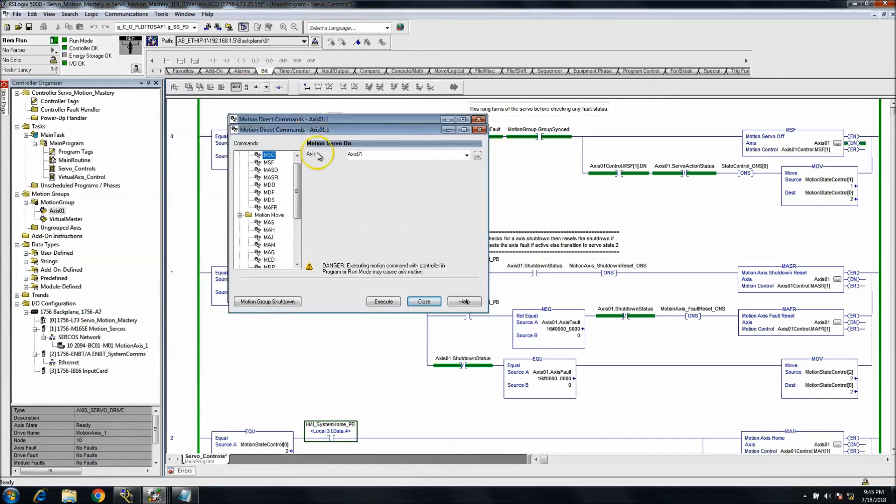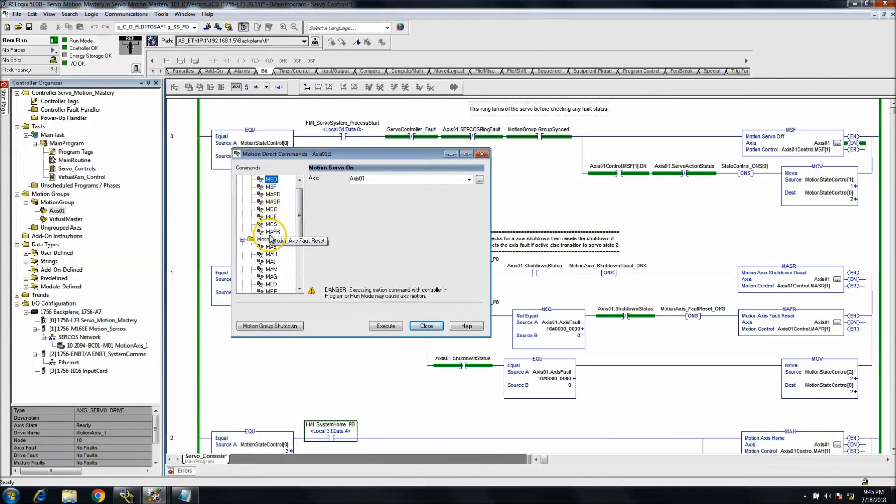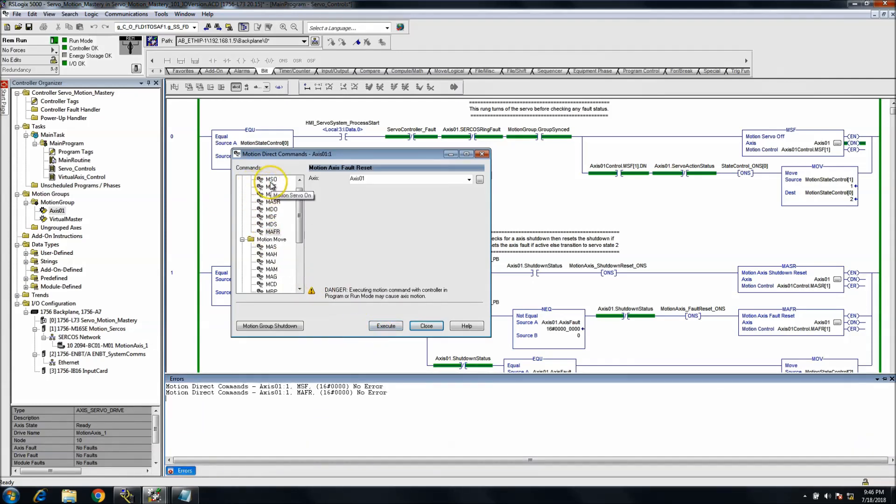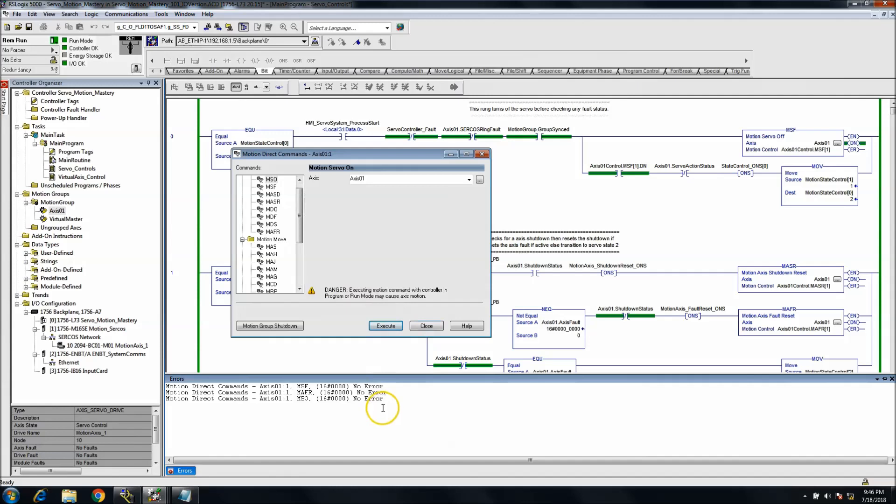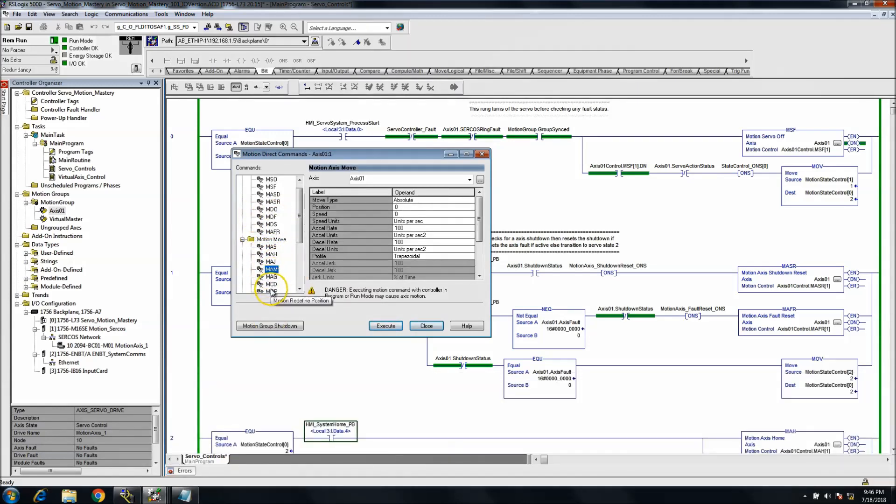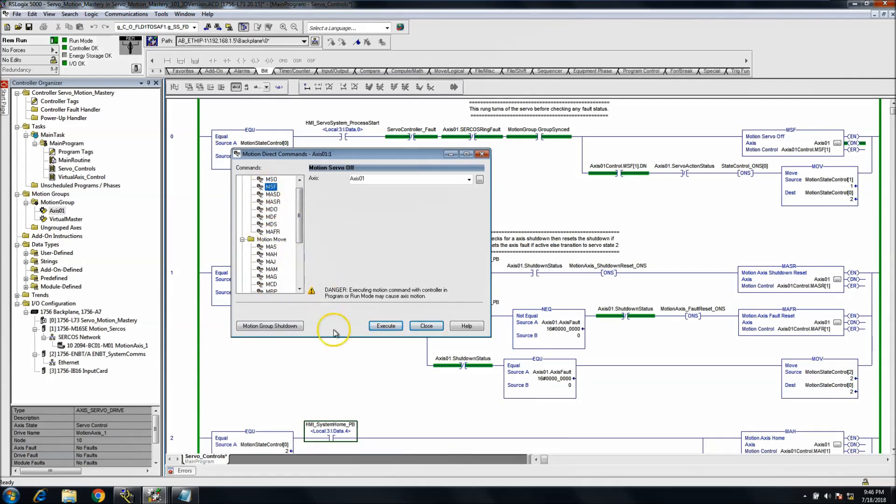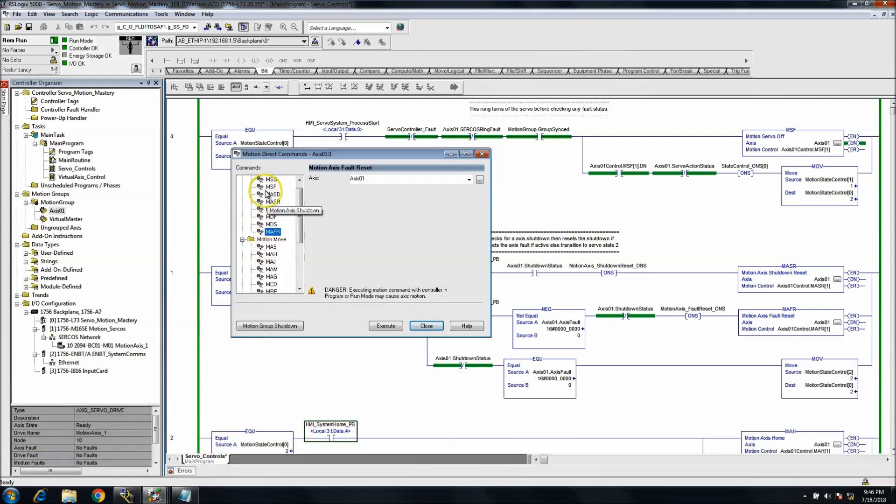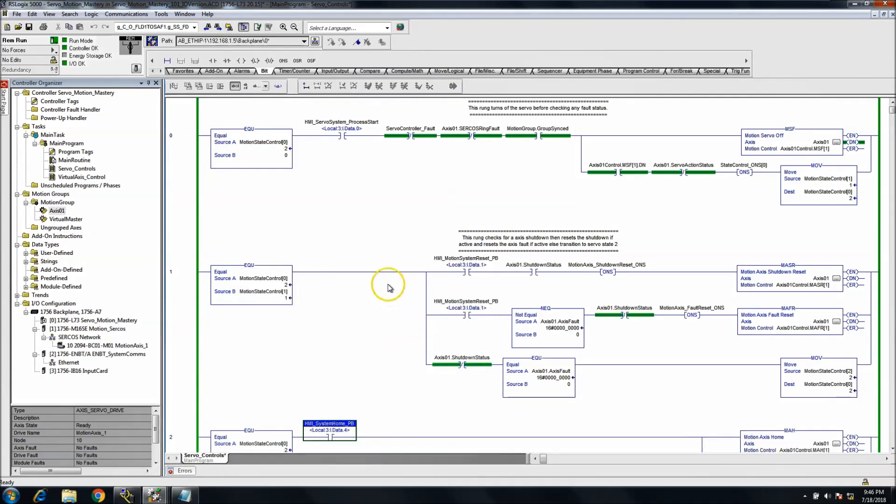If we look at it, if we did a motion axis direct command, the first thing we're going to do is we're going to do an OFF. We're going to make sure it's OFF, we're going to make sure we fault reset it just to do it. We're going to make sure that the system is 100% healthy and then we're going to do an ON. So as soon as it cuts ON then we can actually do a jog or a MAM or whatever we want to do. But the very first thing we want to do is make sure we cut it OFF, we reset it, and then we cut it ON. So why would we choose to ignore those same things when we're trying to do that naturally? That wouldn't be right.